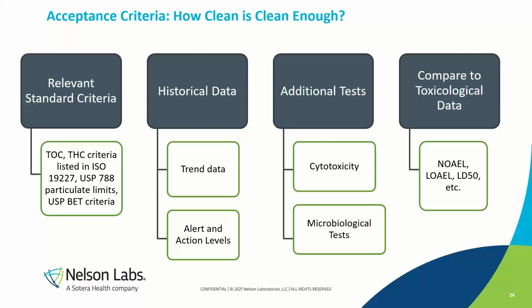So this just involves a bit more research on those chemicals found during the risk assessment of the device, and the databases available, like PubChem and that type of thing. Finding the best available threshold, like the NOAEL value, no observable adverse effect level, or low observable adverse effect level, or LD50, that's lethal dosage of 50% of population. So you find the one that's the most conservative, apply the device use to that calculation and establish a threshold.